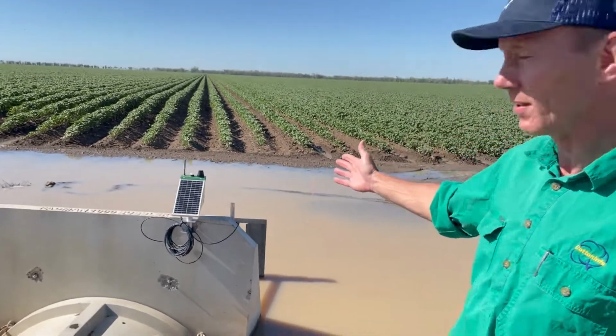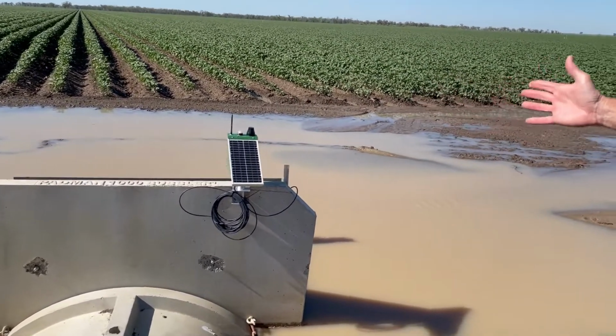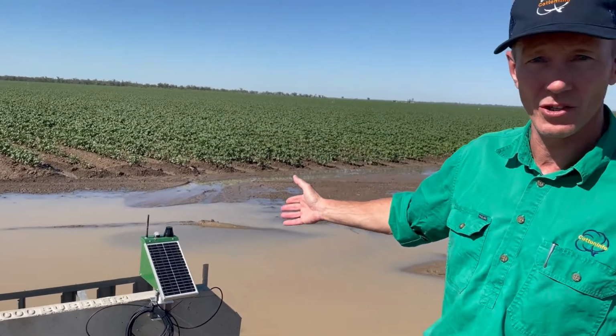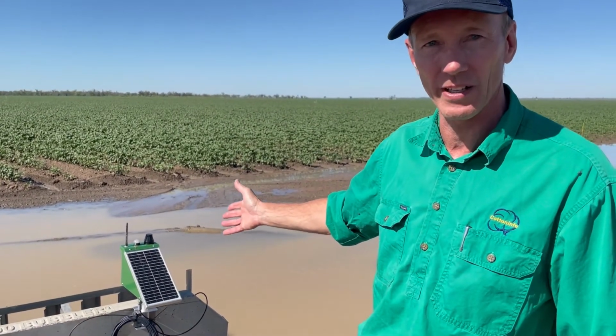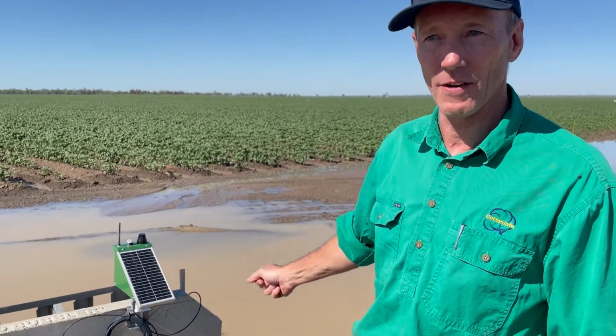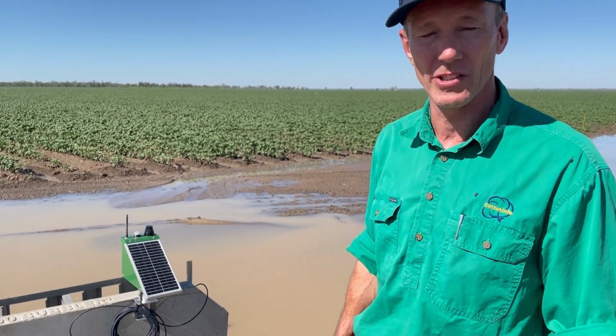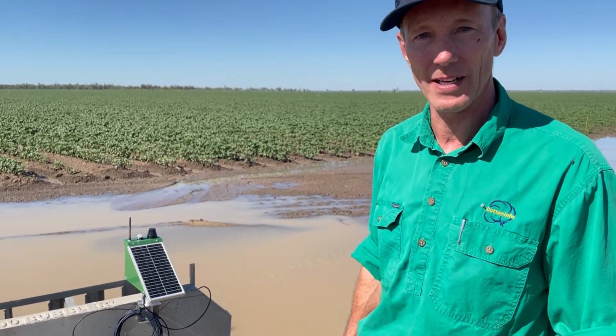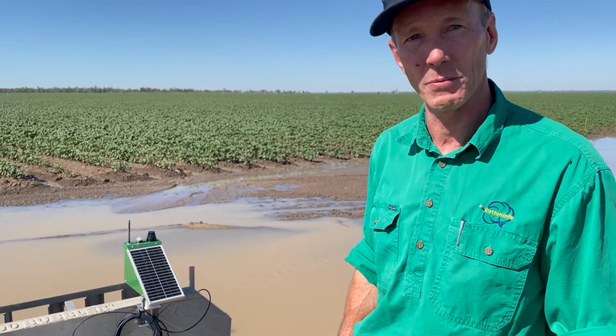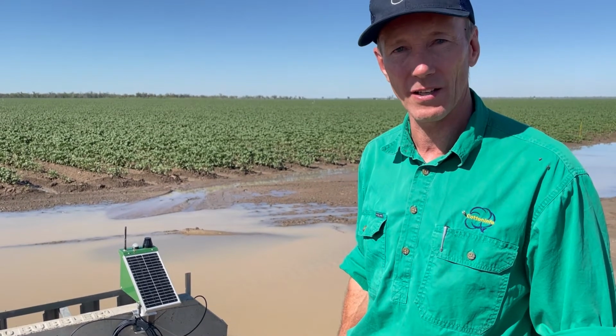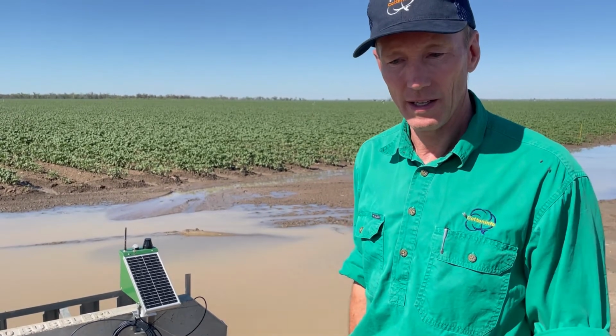What we've got behind me is actually the transmission unit, but attached to that transmission unit is a thing called a Doppler ultrasonic sensor, and it can measure flow velocity of water. Based on the dimensions and shape of the pipe, they can do some calculations to calibrate it, so we know the volume of water and the flow rate coming into the bay at any given time. That allows us to calculate how much water is going down per furrow as part of the calculations we'll need for the efficiency parameters and indices that will be calculated at the end of the trial.